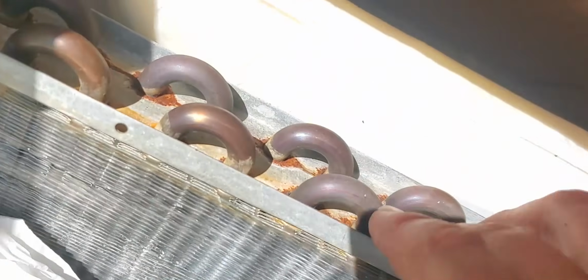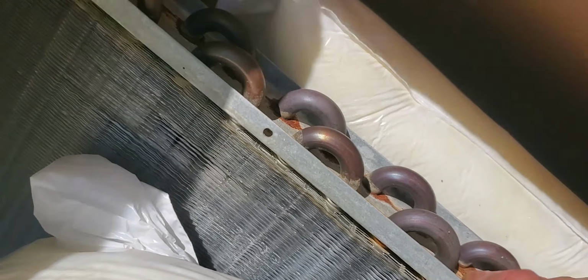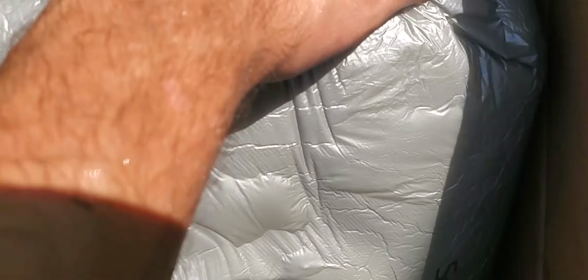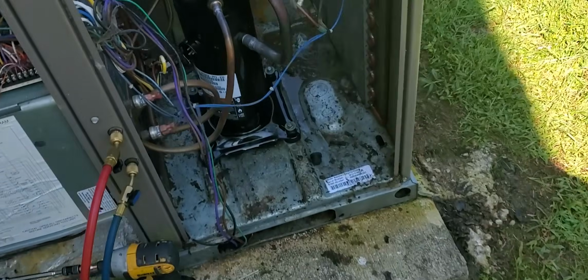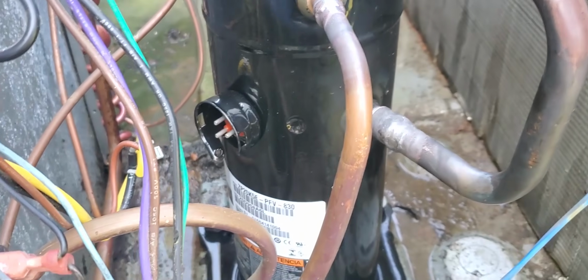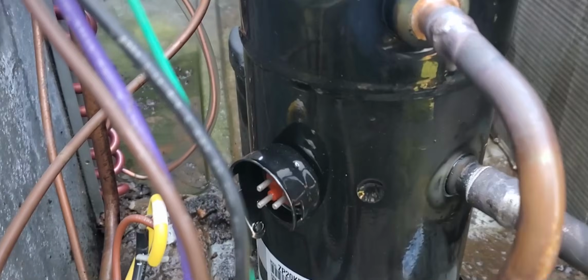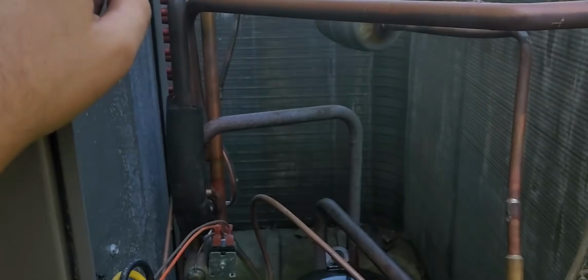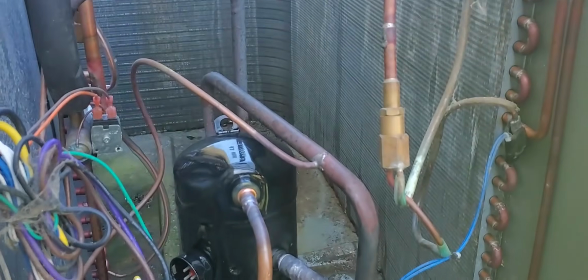See, this old coil does not have. See that? That's the old coil. And then got the old compressor in here. See, it's quite large. Quite large Copeland scroll, same size as far as capacity, but this compressor is quite smaller. Look at that. New compressor's in, new coil's in, filter dryer's replaced. Now I gotta change the fan motor and have this thing back up and running.